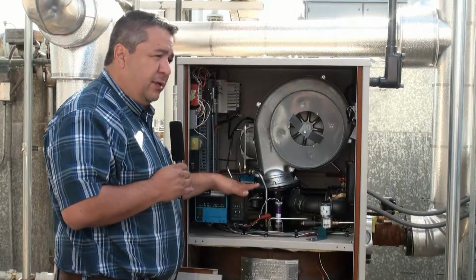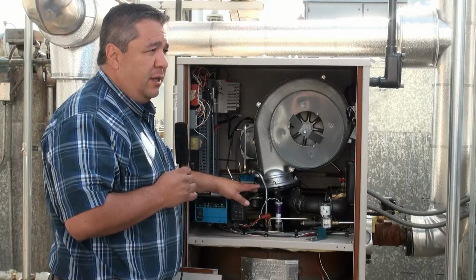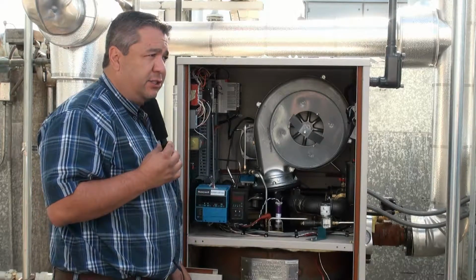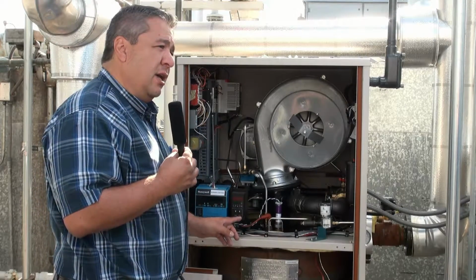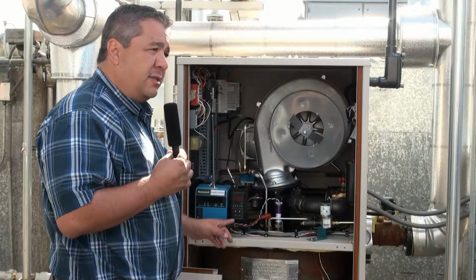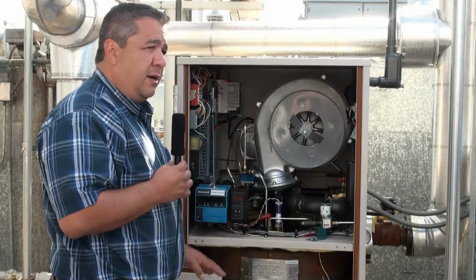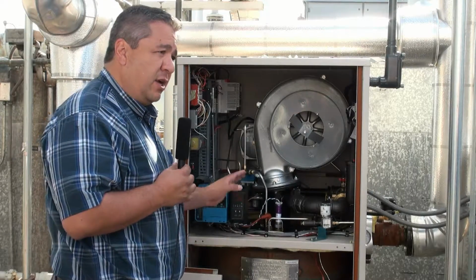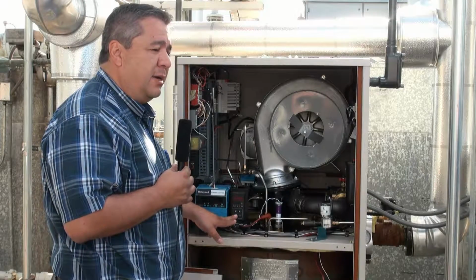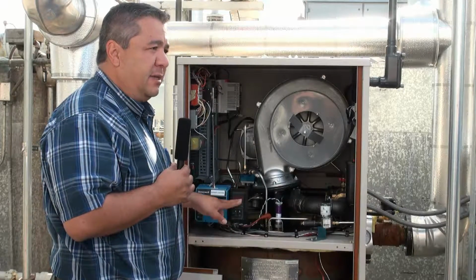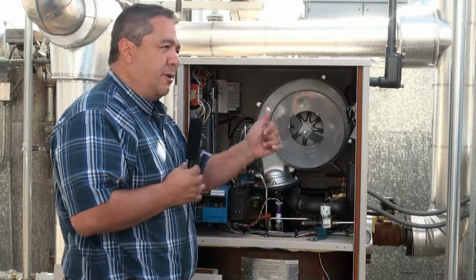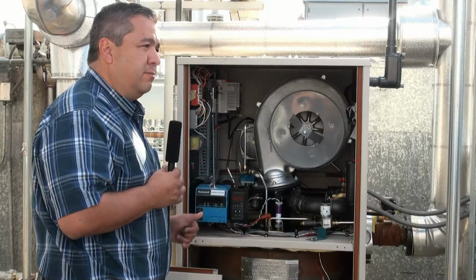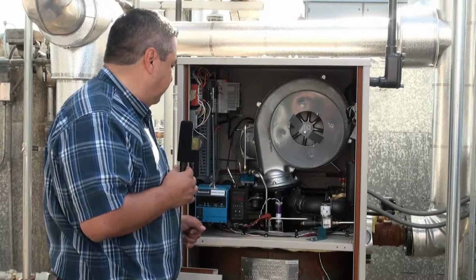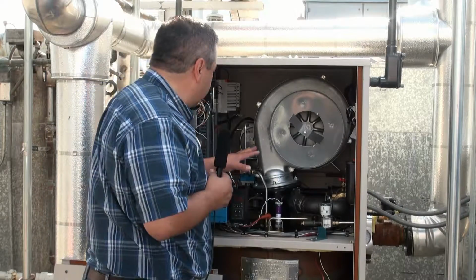You have the ability to control the temperature on this unit. Even though the controls are doing it too, you can adjust the temperature yourself on the keypad if you want. There's instructions in the IOM showing you how to do it. It's really easy - you just hold the program key button down for 3 seconds, it'll tell you the set point, and then you go up and down to what you want it to be.